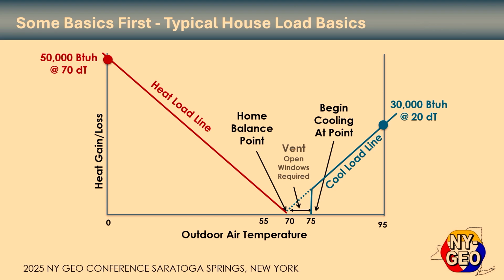So what you're looking at here maybe looks like a complicated chart, but you've got a heat load line here, this red line, and the cooling load line is the blue line over there. And we assume that you start with a 70-degree thermostat set point roughly, and outdoor temperature, then you go from there. And that's how you get your cooling and heating load lines, with your heat loss, 50,000 at 70 degrees, for example, here, and 30,000 at 20.